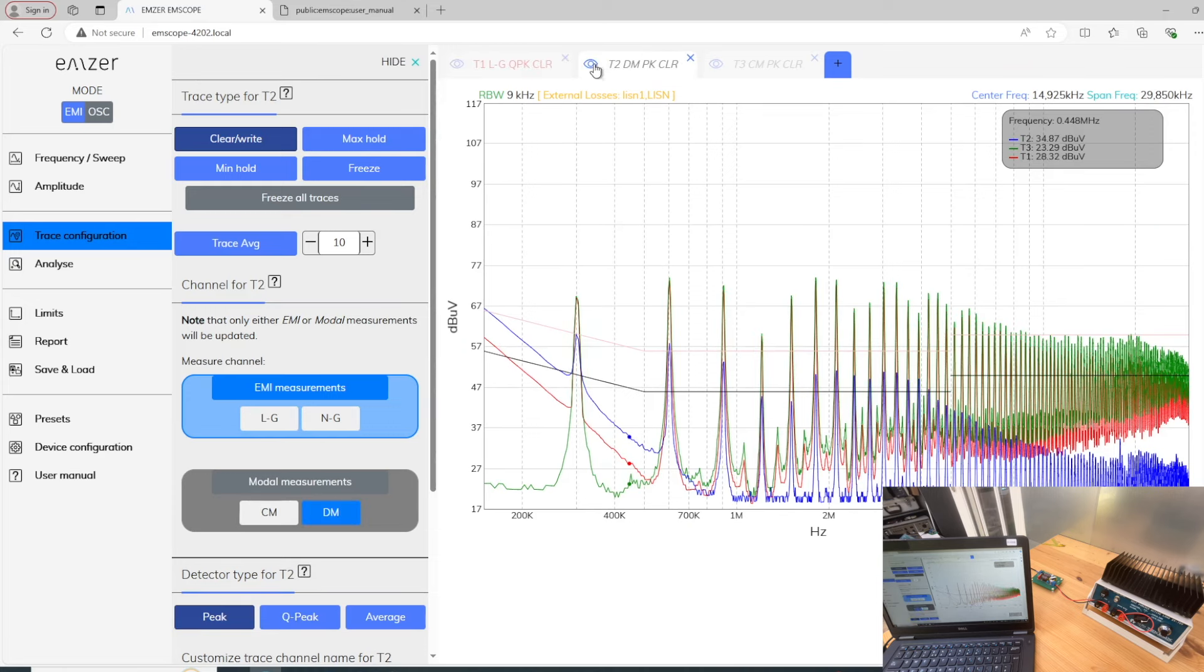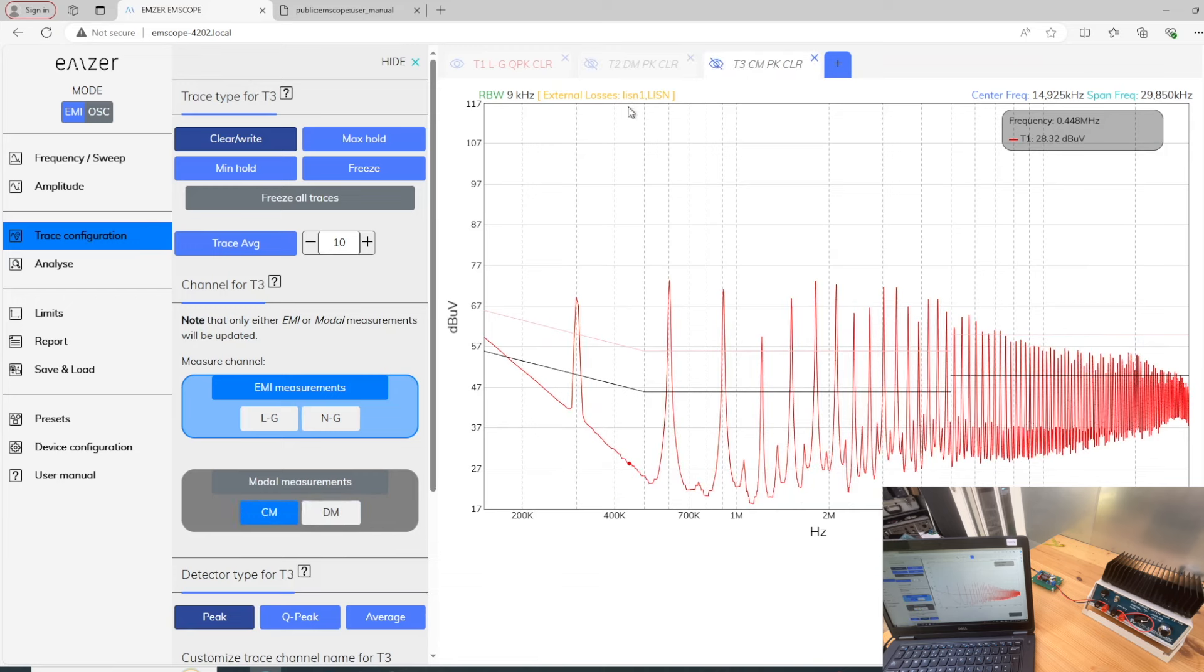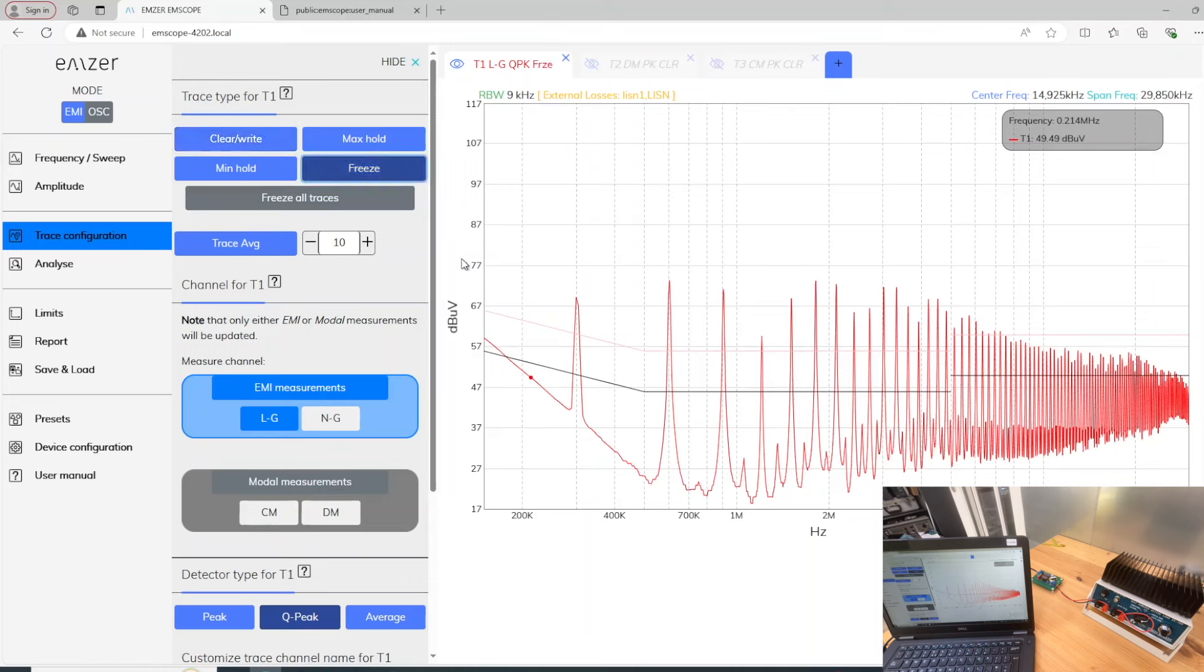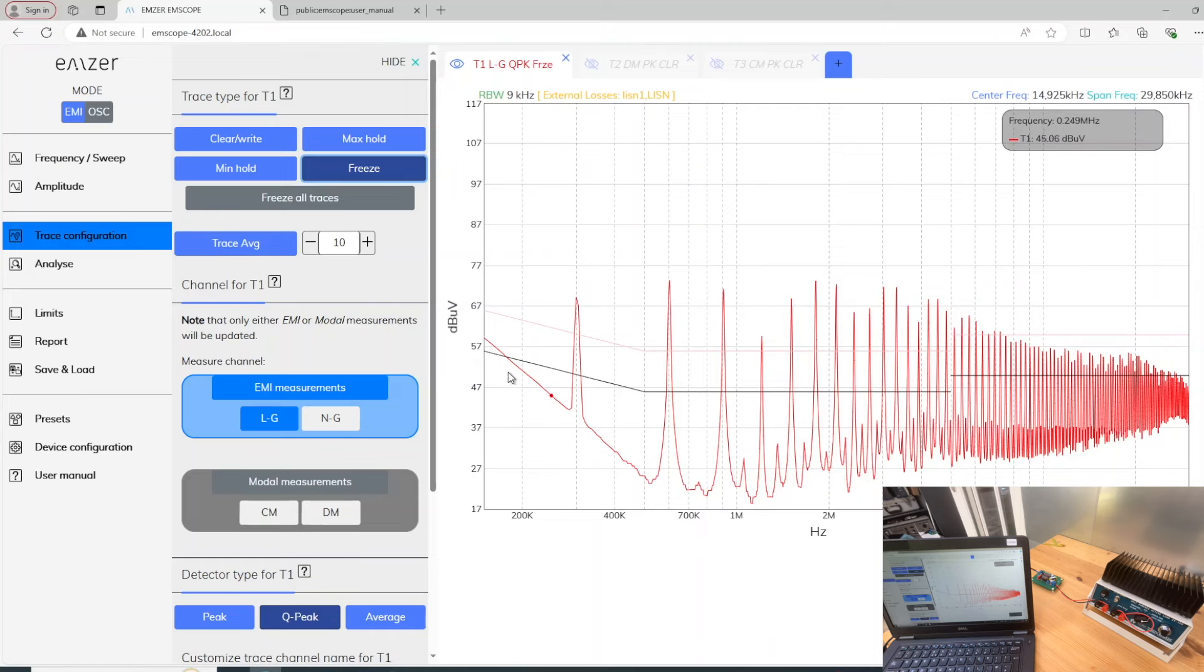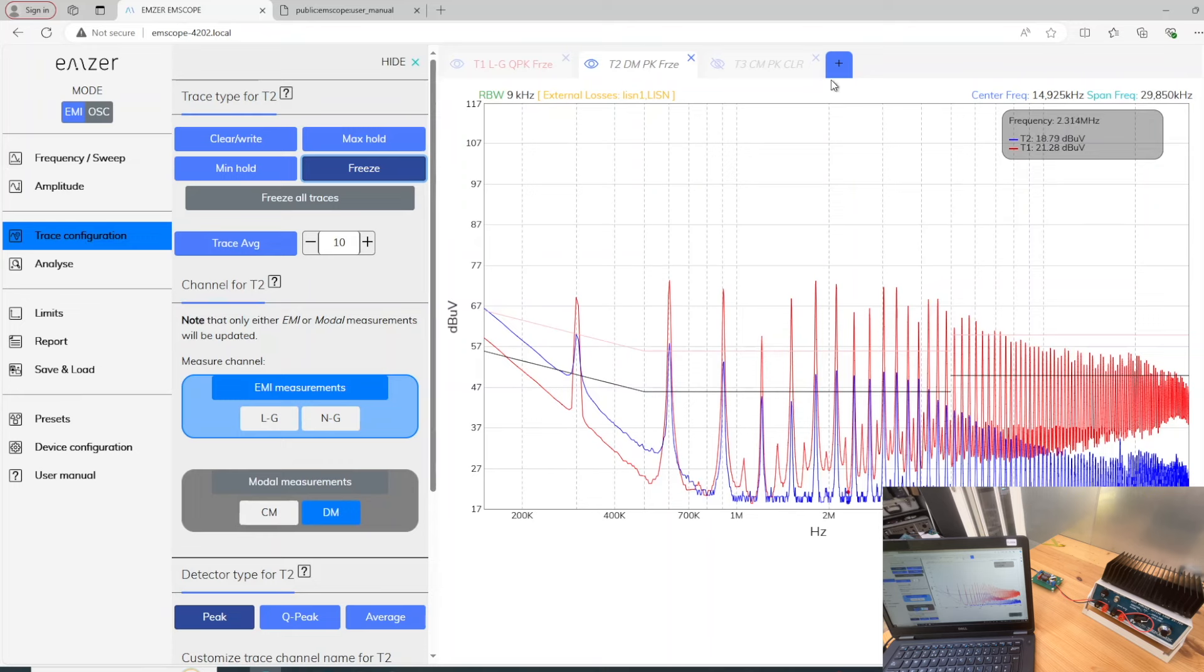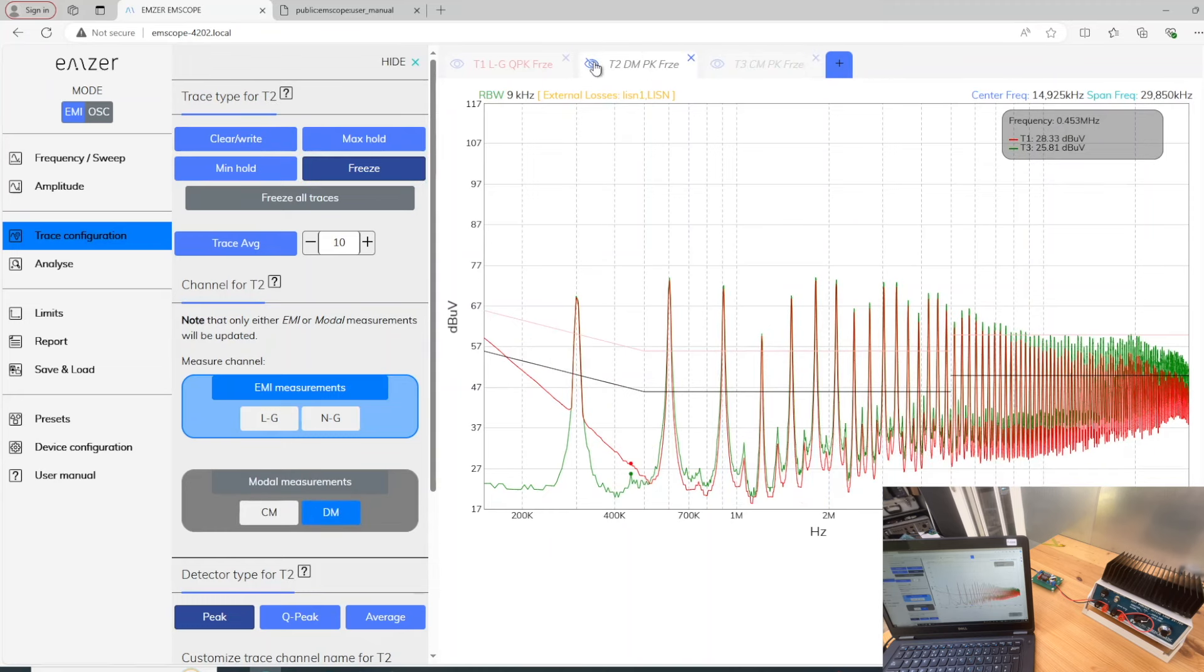Now we have three results here. Another feature here, you can see that I can hide these two, I'm only showing this one. This is really the overall conducting emission results measured by the analyzer. I can freeze it. Now it's frozen. You can see definitely quasi peak results exceeding the quasi peak limit line in this case by a few dB, actually pretty bad. Interesting. If I put in here and I show you the differential mode noise, the differential mode noise I freeze it is this level, whereas the common mode noise...